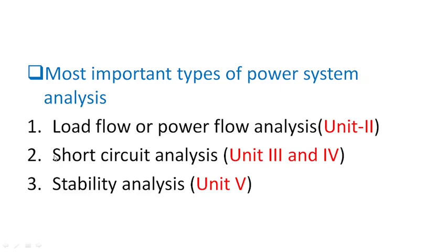Second analysis is short circuit analysis. This short circuit analysis gives results to design the circuit breaker and protective schemes. The circuit breaker and protective schemes ensure protection of the power system under abnormal conditions. For example, if there is any fault in any part of a power system, that should be cleared as soon as possible, or that part should be disconnected from the healthy part as soon as possible.